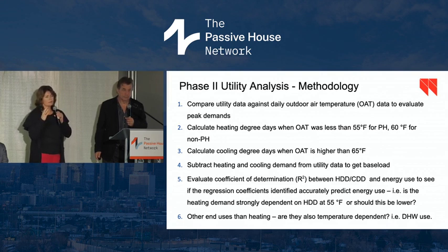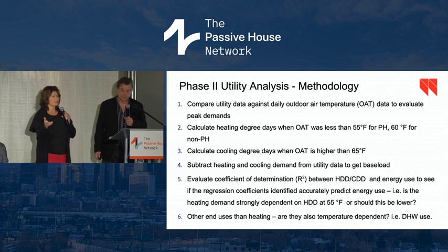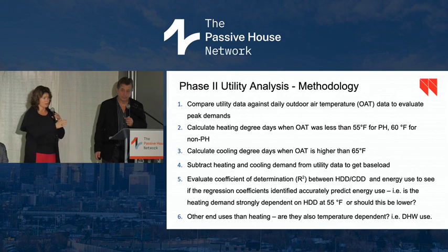What you have to understand about Passive House projects is they do not respond to outdoor temperature like older buildings. Older buildings respond when it hits 65 degrees and lower, heat starts to kick in. These buildings do not, so we have to figure out what balance point temperature to use for heating. We used 55 and below to calculate heating degree days, because that's when they turn their heat over.